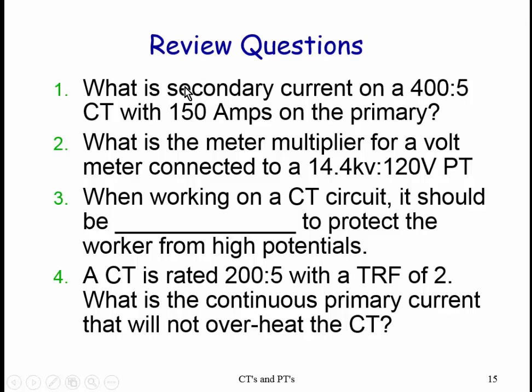All right, so here's a few questions for you. What's the secondary current on a 400 to 5 CT? Now that's a ratio of 80, right? 400 to 5 is a ratio of 80. If there's 150 amps on the primary, just divide that by 80, and you will quickly determine that it is 1.88 amps, right? I mean, if I had 400 amps, I'd have 5 on the secondary. If I had 200 amps, I'd have 2.5, right? So you know it's going to be less than 2. So anyway, I got 1.9 roughly. Okay, let's skip that one.